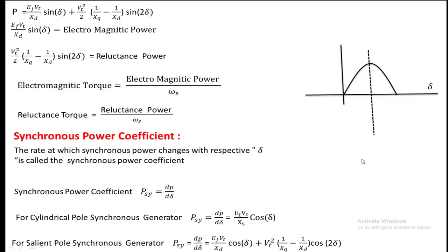For the cylindrical rotor, delta is on the x-axis and power on the y-axis. If you differentiate the P vs. delta curve with respect to delta you get the synchronous power coefficient, which follows a cosine profile. If the synchronous power coefficient is positive, the machine is stable; if negative, it is unstable. As long as delta is less than 90 degrees, whether the machine is a generator or a motor, it will be in the stable region; otherwise the machine becomes unstable.